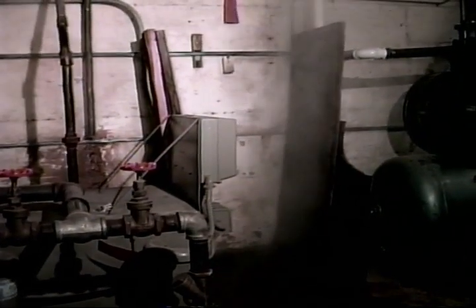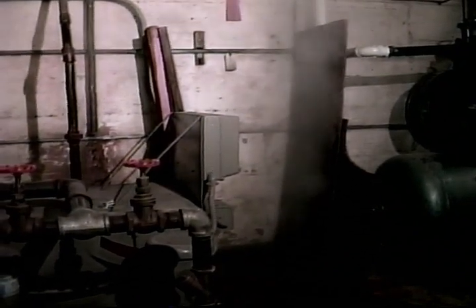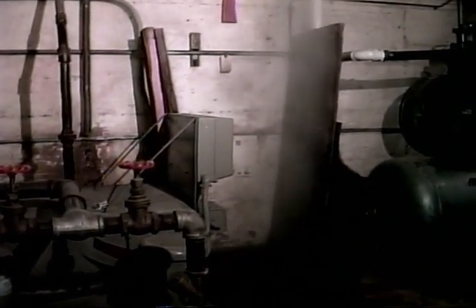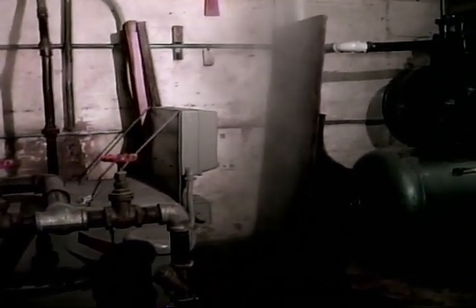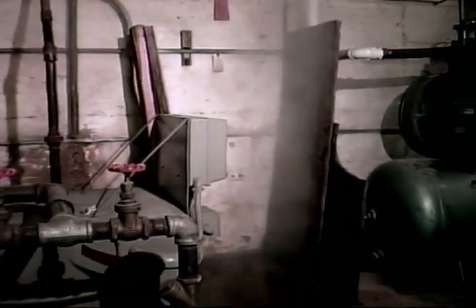This is a condensate receiver. In a steam heating system, as the steam cools, it condenses and forms water. The traps in the system return this water to this receiver. As you can see, we've got live steam coming out of this receiver, which is not supposed to happen. The traps are malfunctioning and are allowing this steam to escape through them into the receiver system.